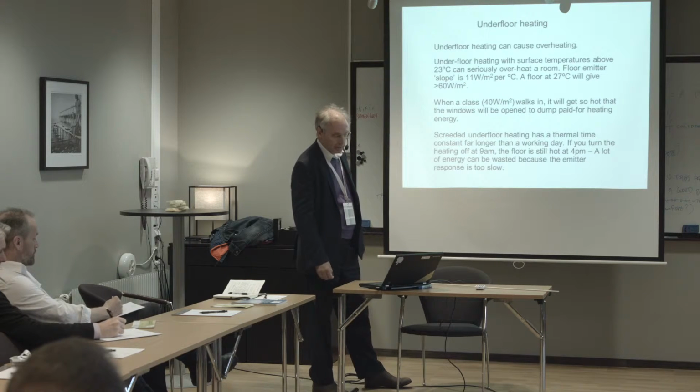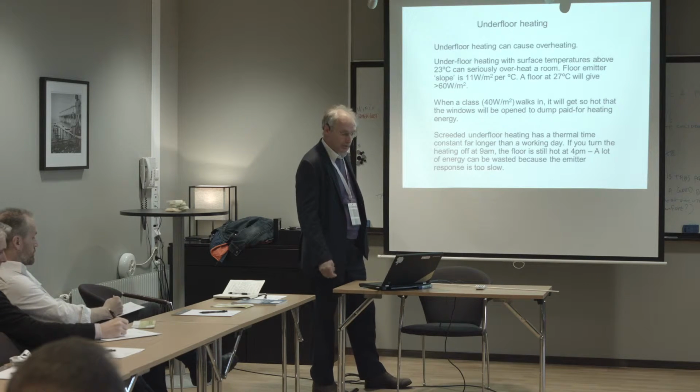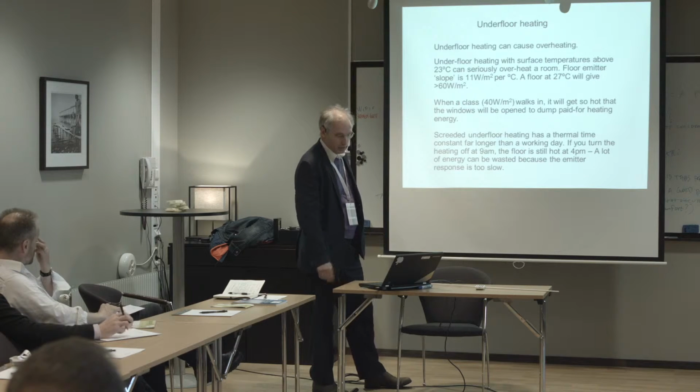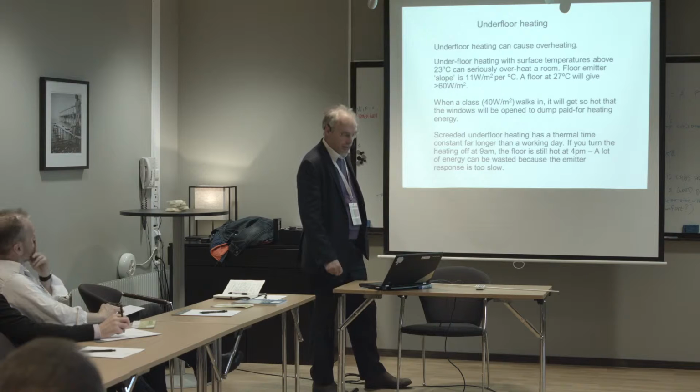Underfloor heating, I think we just mentioned that can cause a big problem because we've got the floor emitter slope 11 watts per square metre per degree C. So a floor of 27 degrees gives off 60 watts per square metre.